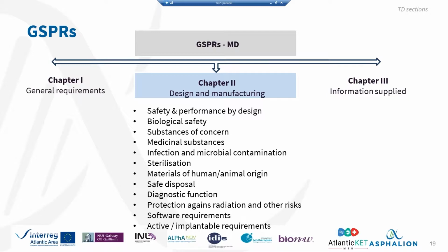Well, safety and performance by design. You've got to design your device so that it is safe from its conception. Okay. Biological safety, you've got to test biocompatibility of your device, obviously. Substances of concern, you've got to see if your device has leachables or extractables, or substances that could have an adverse effect on the patient. You've got to assess if your device includes or doesn't include medicinal substances which are ancillary.